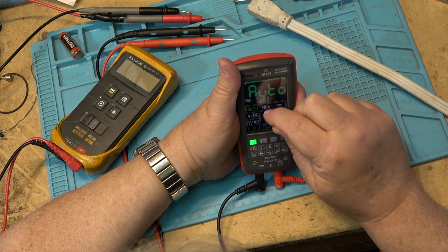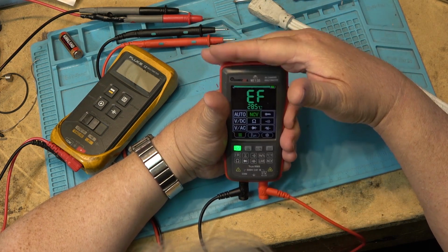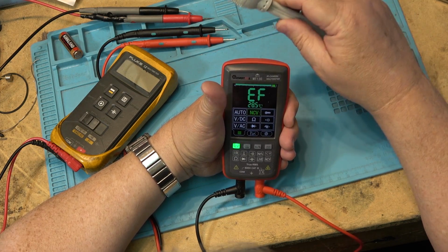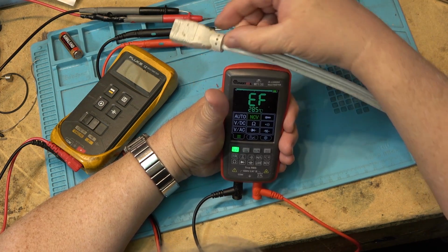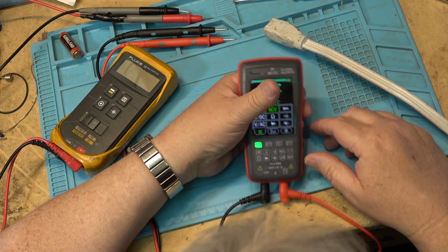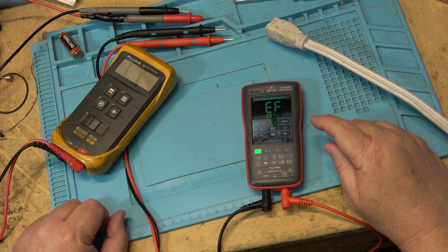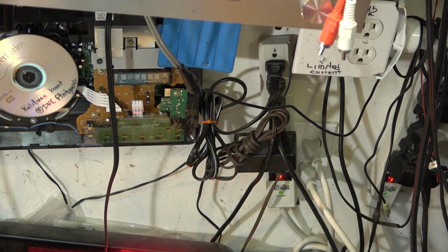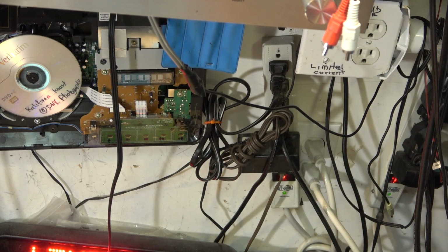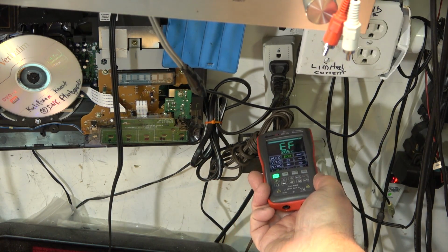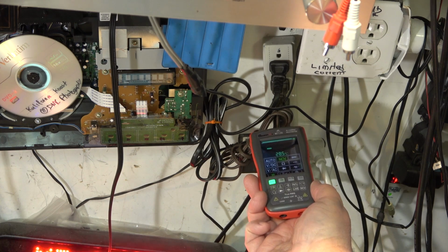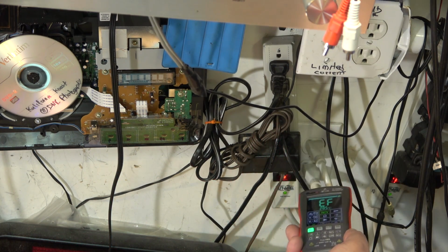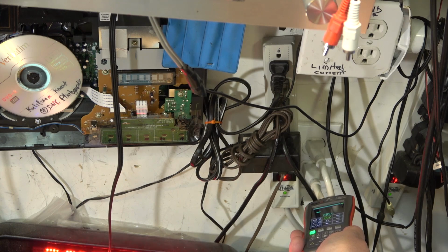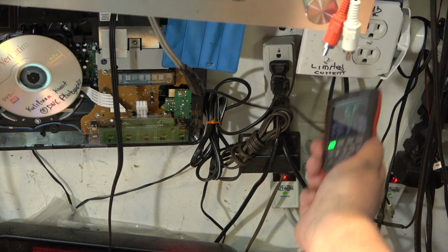Non-contact voltage detection. We can tap here, and the non-contact range is up top here. So if I bring something that's emitting, this probably won't because it's on an isolation transformer, so I doubt this one will. But if I bring this near something that is not on an isolation transformer, we should detect. For example, I can bring the meter with or without probes. I can take the probes out for this. If I'm just looking to see if there's any voltage, I can detect induction near a wire that's live. So that will tell you if you've got an outlet that's live or not.